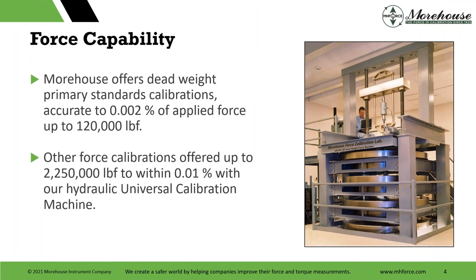And we have deadweight standards accurate to better than 0.002% of applied force, up to 120,000 pounds of force. Most people we find that have calibrating machines, some customers have 500,000, 300,000, or million pound machines. Most are operating in some sort of range of 100,000, 30,000, even 10,000. And then below that, we pick up with our PCM. However, we do offer force calibrations. I know it's rare, but for the handful of companies we do business with, we go up to 2.25 million pounds of force, or 10 meganewton.